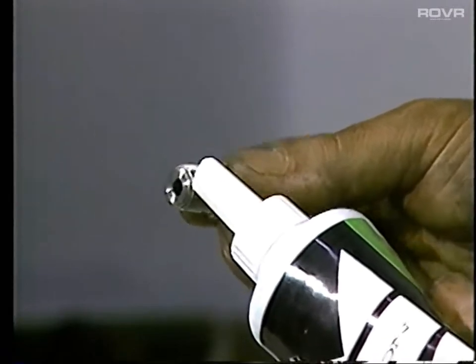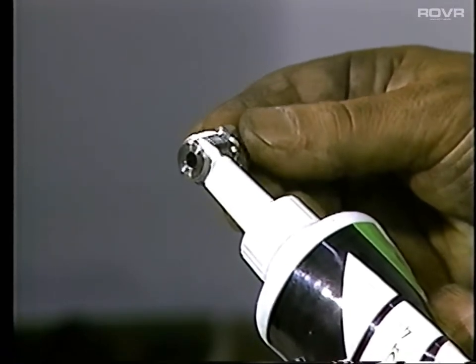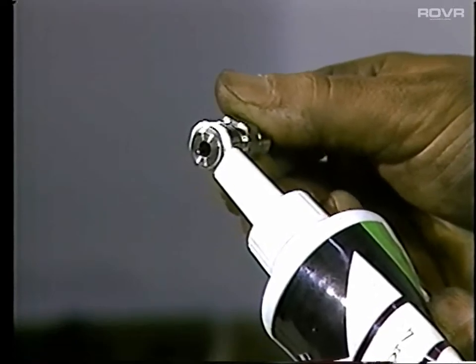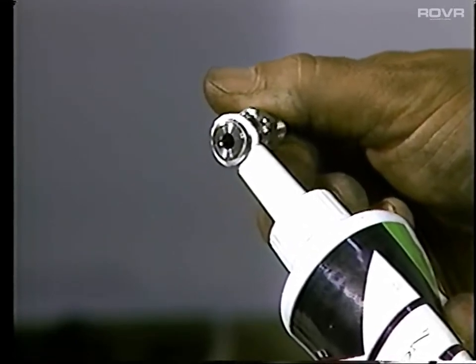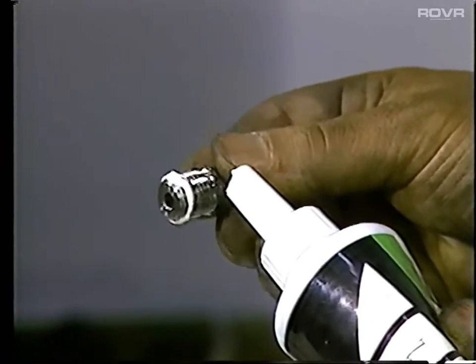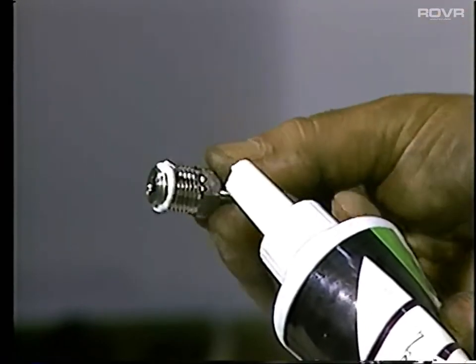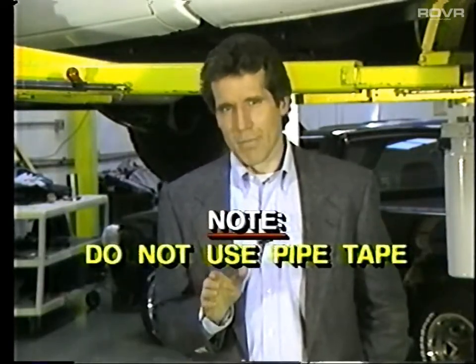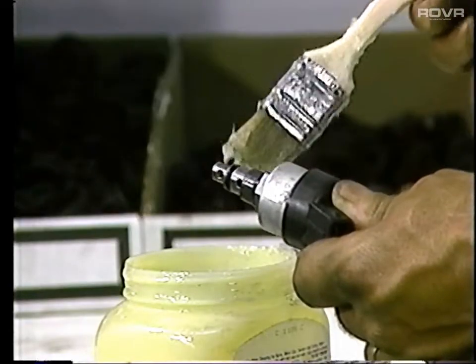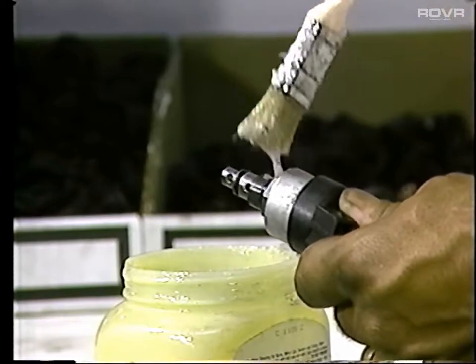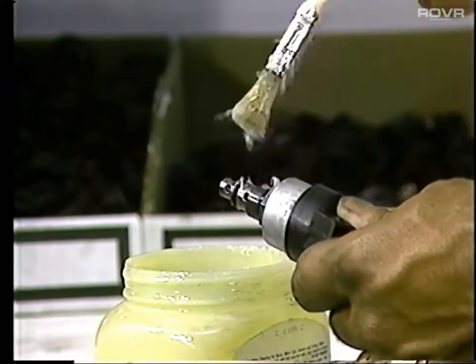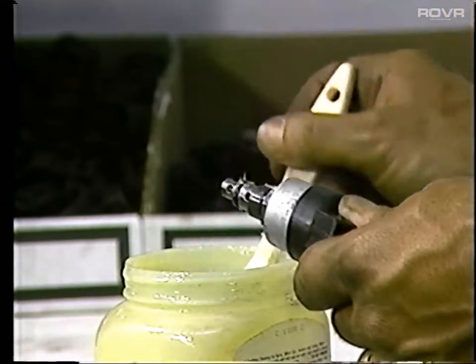And while we're speaking of the sealer, let me show you another important precautionary procedure. Always apply the pipe sealer over the first few threads of the male component. The sealer will hold any burrs or debris that may break loose while threading the components together. The sealant will seize the debris, keeping it from becoming a gas-borne contaminant downstream of the system. Note, do not use pipe tape because it's been known to have fragments break loose and get into the system. When connecting components with O-rings, always cover the rings with petroleum jelly. This prevents the rings from rolling or chafing when the parts are joined.